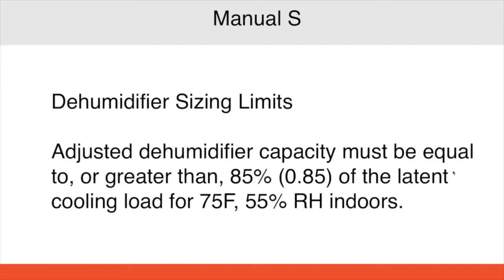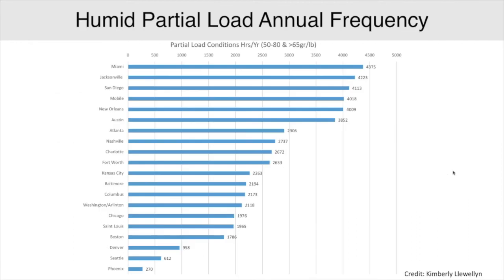So dehumidifier sizing limits: you need to adjust, and the dehumidifier capacity must be equal to or greater than 85% of the latent cooling load for that 75 degrees and 55% RH indoors. So again, this all is in Manual S. It starts on page 49. So what's interesting again is when we talk about sizing dehumidifiers and getting our Manual J load conditions at peak conditions.